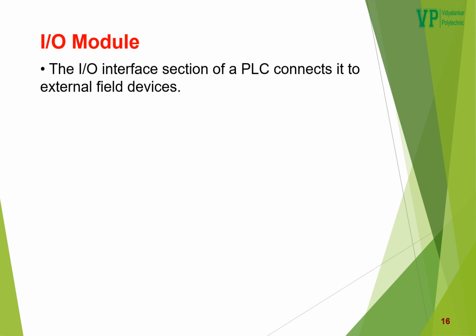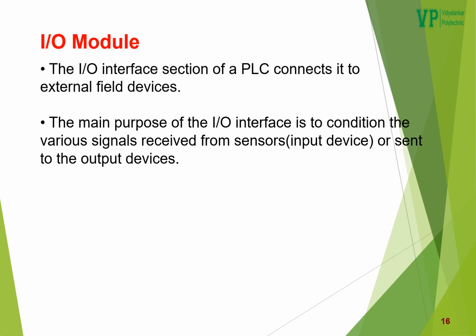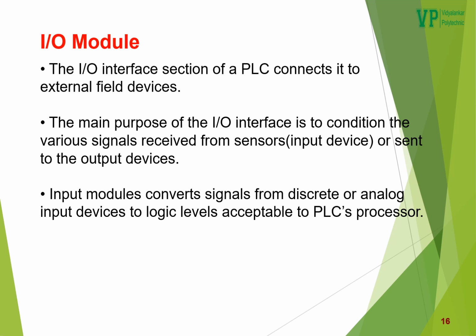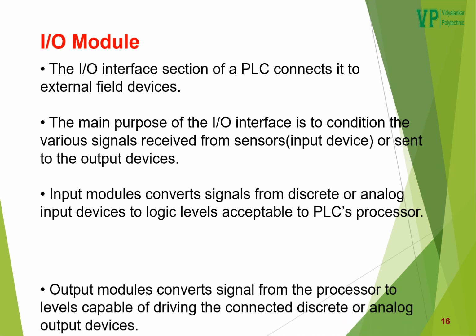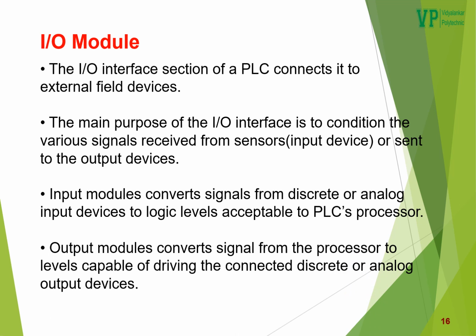The input-output module. The I/O interface section of PLC connects it to the external field devices. The main purpose of the I/O interface is to condition the various signals received from sensors, that is input device, or sent to the output devices. Input modules convert signals from discrete or analog input devices to logic levels acceptable to PLC's processor. Output modules convert signals from the processor to levels capable of driving the connected discrete or analog output devices.